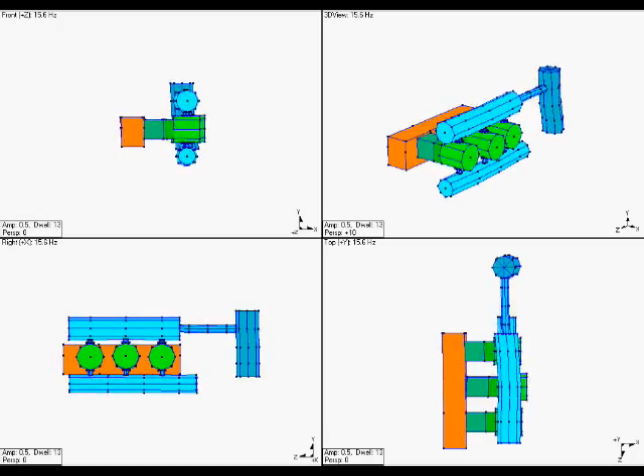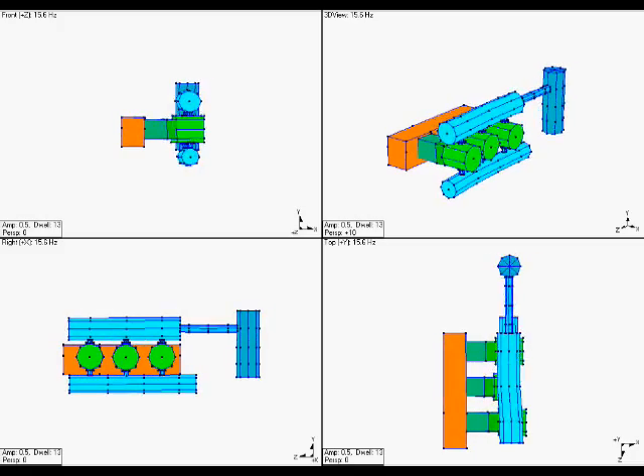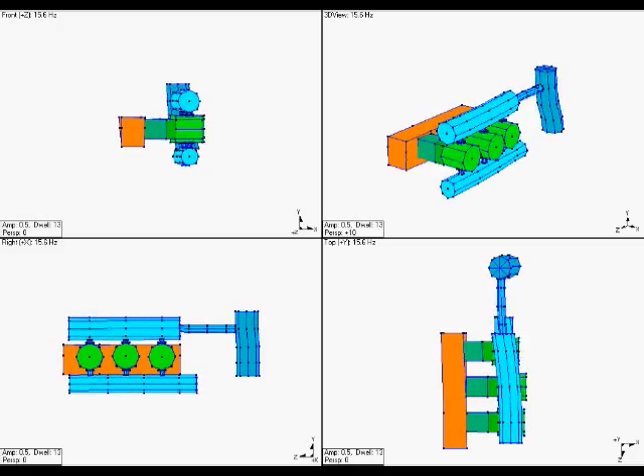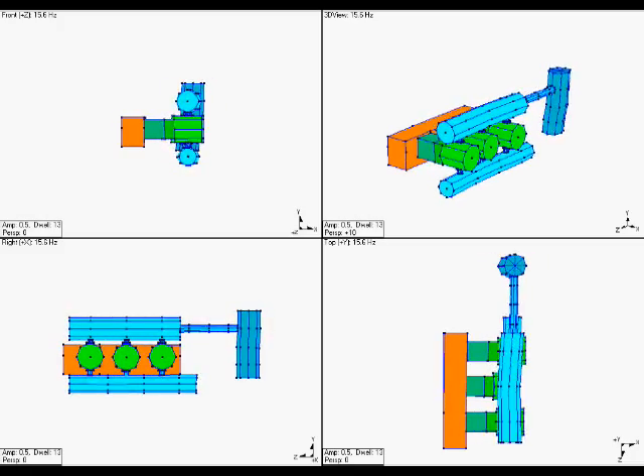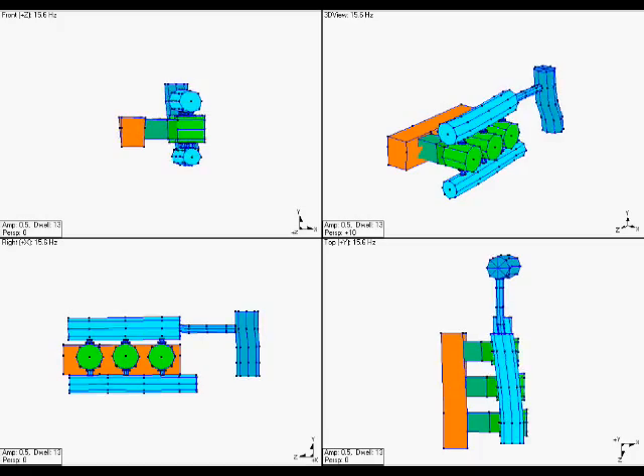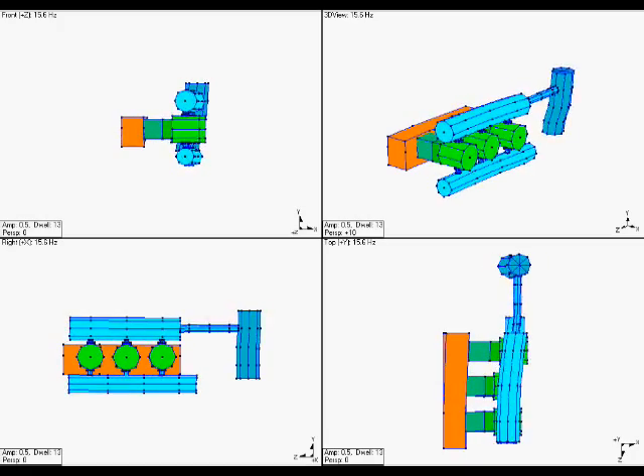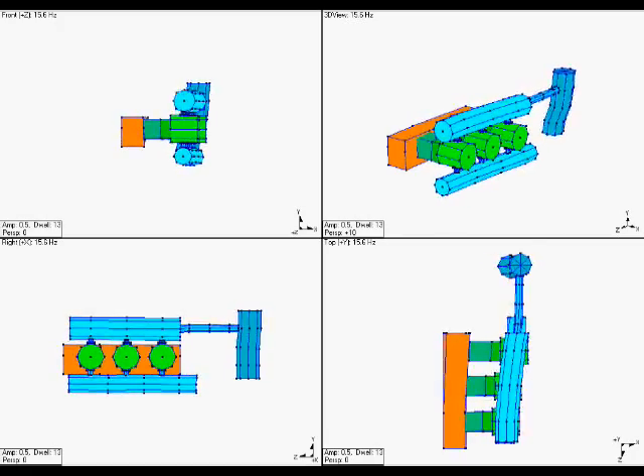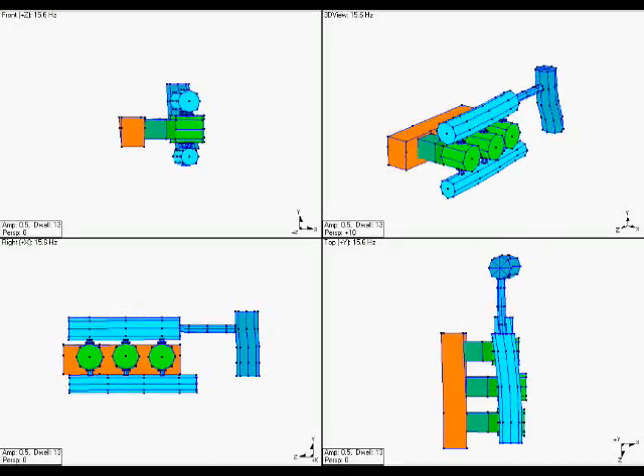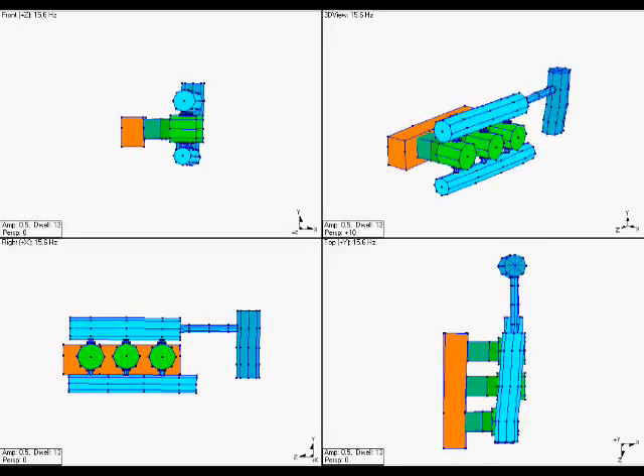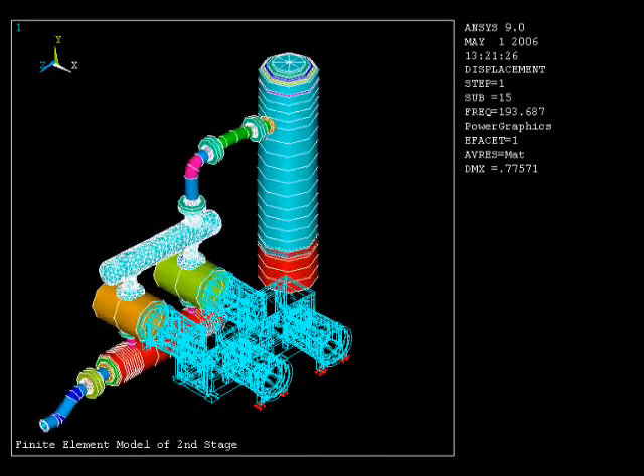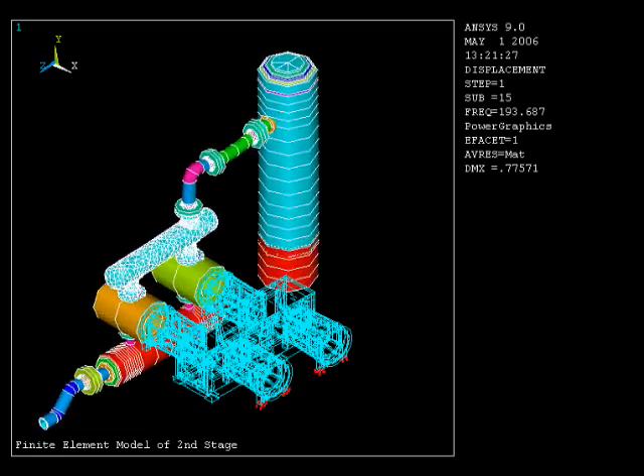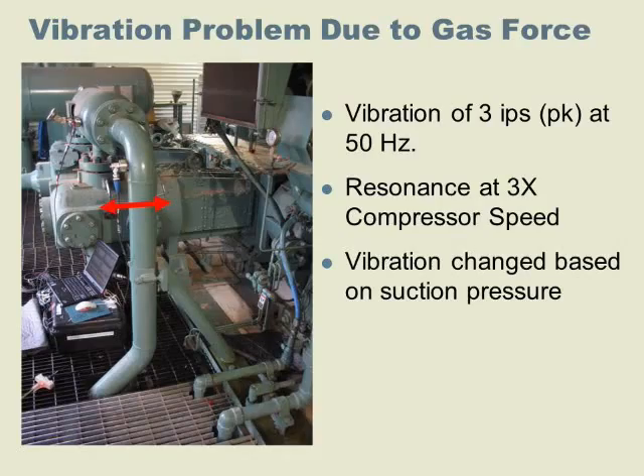Cylinder gas forces will cause each cylinder to move and in turn cause piping and bottles to vibrate. Notice how the scrubber and bottles will move in phase with the cylinder motion. If the natural frequency of the piping system coincides with the frequency of the gas forces, then resonance will occur and amplify the vibration.